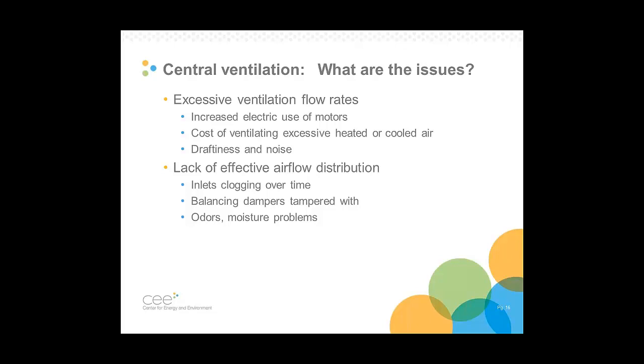Lack of effective airflow distribution is another issue, where there can be areas of high ventilation and low ventilation or no ventilation. Reasons for this: inlets can clog up over time. Balancing dampers, the devices that are meant to deliver even flow throughout the building, might be altered. Residents or occupants may alter them. And then the result is that there can be odors or moisture problems in areas where there's low or no flow.